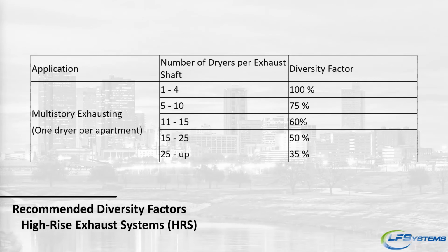And the other thing, especially with dryers, is that that 180 or 200 CFM is the maximum CFM being drawn through the dryer. When the dryer first starts up and the clothes are really wet, there is a lot of resistance in the dryer, so you're not actually pulling as much air at the beginning of the cycle versus at the end. A lot of that can be taken into account when sizing your shaft. So we can size the shaft for 50% diversity and then give you a little extra capacity in the off chance that it goes above that, to make sure that we maintain pressure in the shaft.